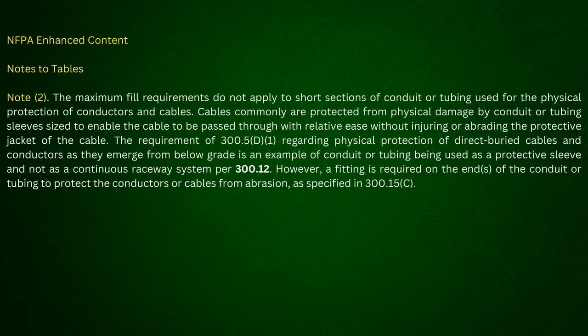And I tell them, if you go in and look at note 4, it says where conduit or tubing nipples, not including connectors, have a maximum length not to exceed 24 inches. Okay. And it says installed between boxes, cabinets, similar closures. It tells you here the nipples shall be permitted filled 60%. They're literally telling you 24 inches or less is considered what? A nipple. Anything above that is what? A raceway. But it's connected from end to end, just like a nipple is. A sleeve is totally different from this.